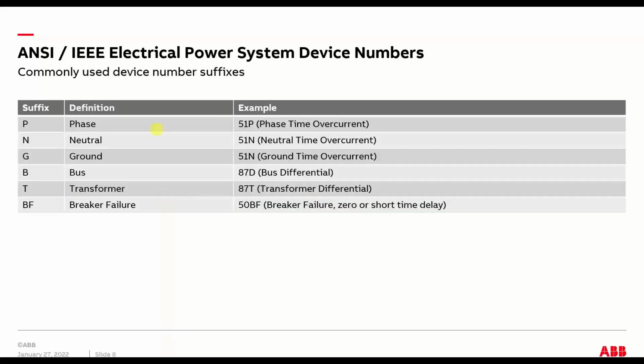Then there are some common suffixes used on those devices, like P for phase. So a 51 time overcurrent with a P means the phase, N for neutral, G for ground, B for bus. There's a typo here. I should say 87B as in boy. T for transformer. That's 87T, transformer differential. BF would be breaker failure.